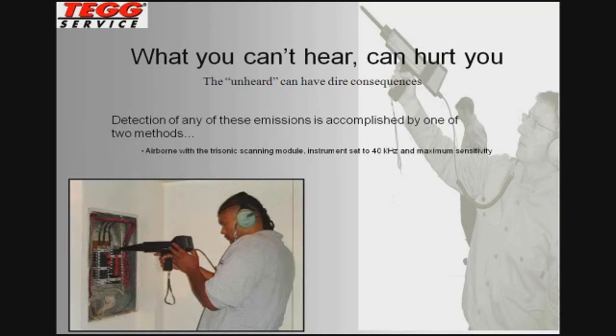Detection of these comes two different ways, as most of you are probably familiar with. The airborne module, which is optimized for 40 kilohertz, and we choose to use it religiously with the rubber focusing cone. There's two reasons for that. Narrowing the field of view makes it much easier to isolate down the source of the emission, and since we're dealing with energized electrical systems, rubber's a good insulator, so it certainly provides a barrier or a shield between the technician that's using the instrument and the component that he may be scanning at that time.